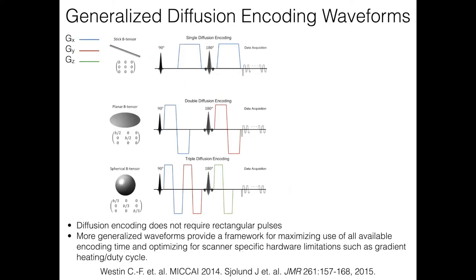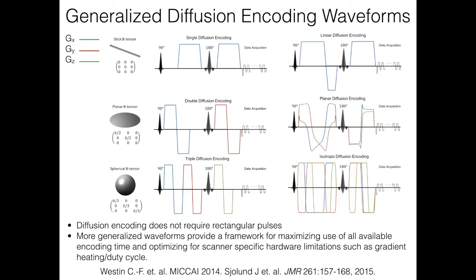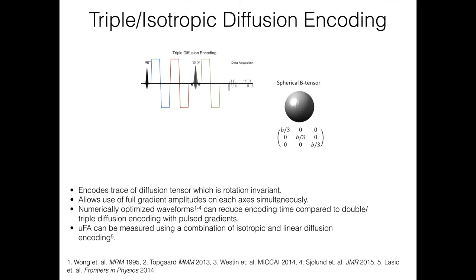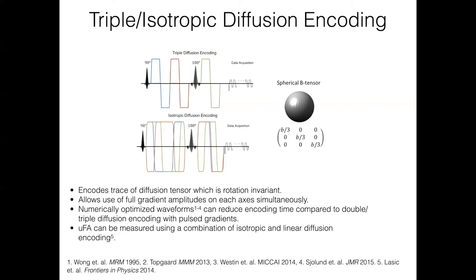Other groups very cleverly realized and proposed more generalized diffusion encoding waveforms. Rather than sticking to rectangular pulses, generalized waveforms provide a framework for maximizing all available encoding time and an opportunity to optimize for scanner-specific hardware limitations such as gradient heating and duty cycle. This is particularly beneficial for triple diffusion encoding — you can play all three axes simultaneously, dramatically reducing the echo time or allowing higher B values.